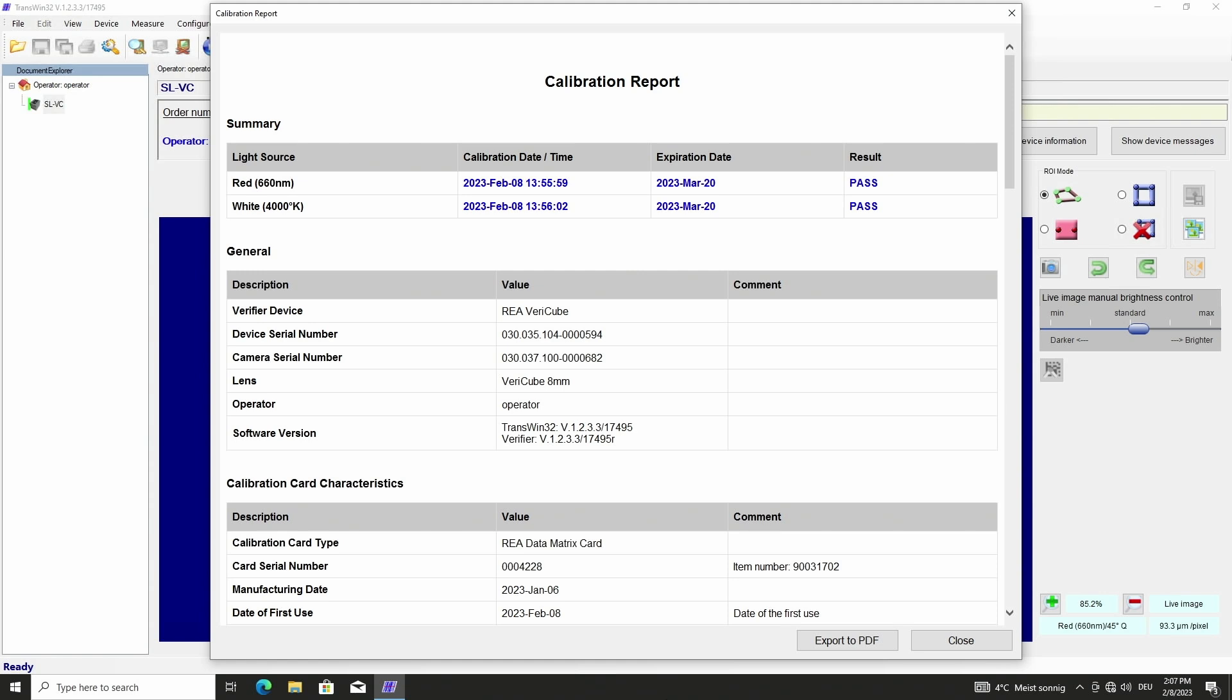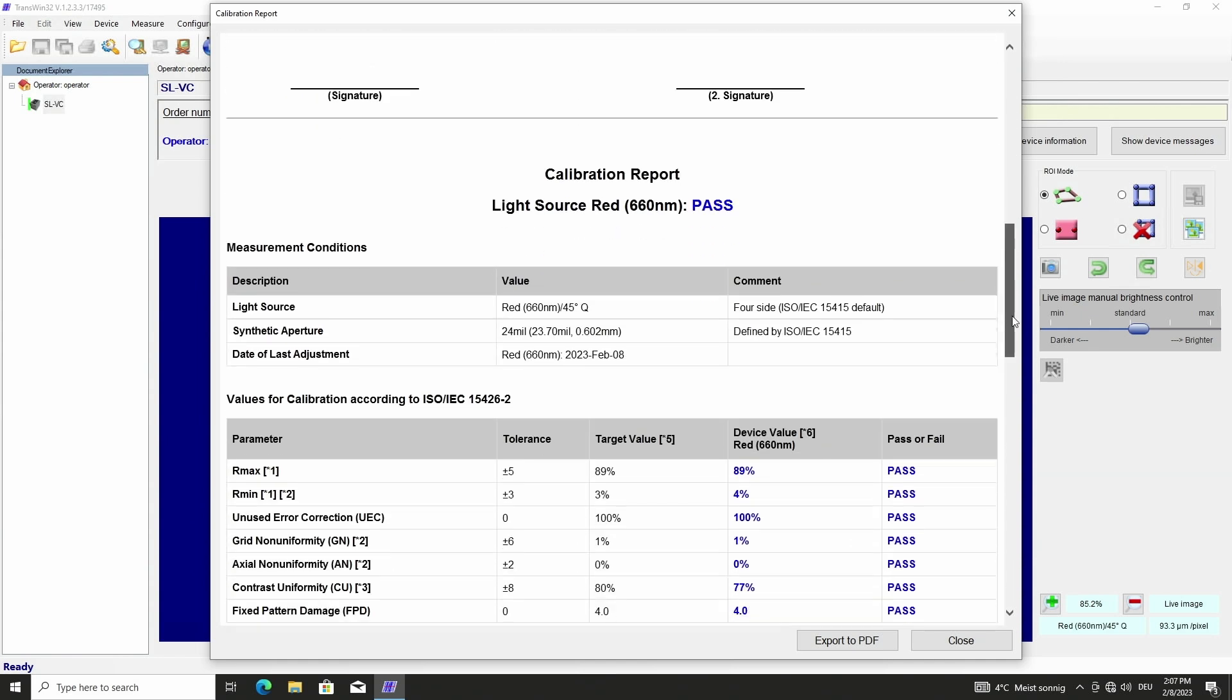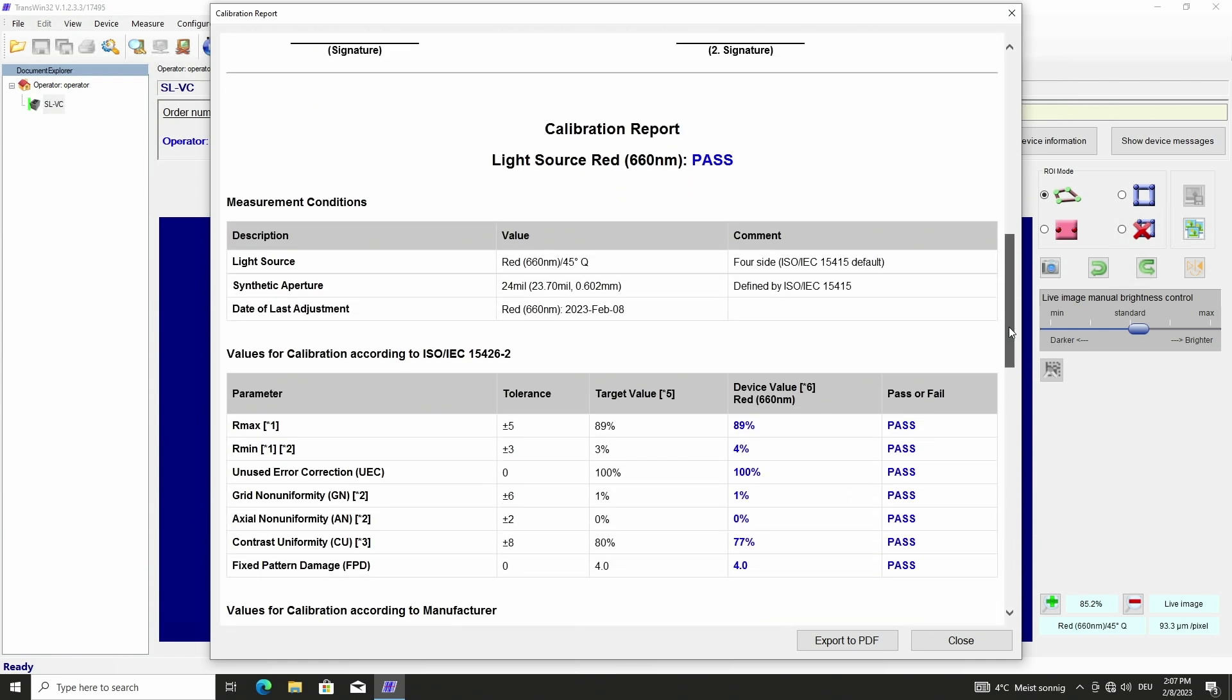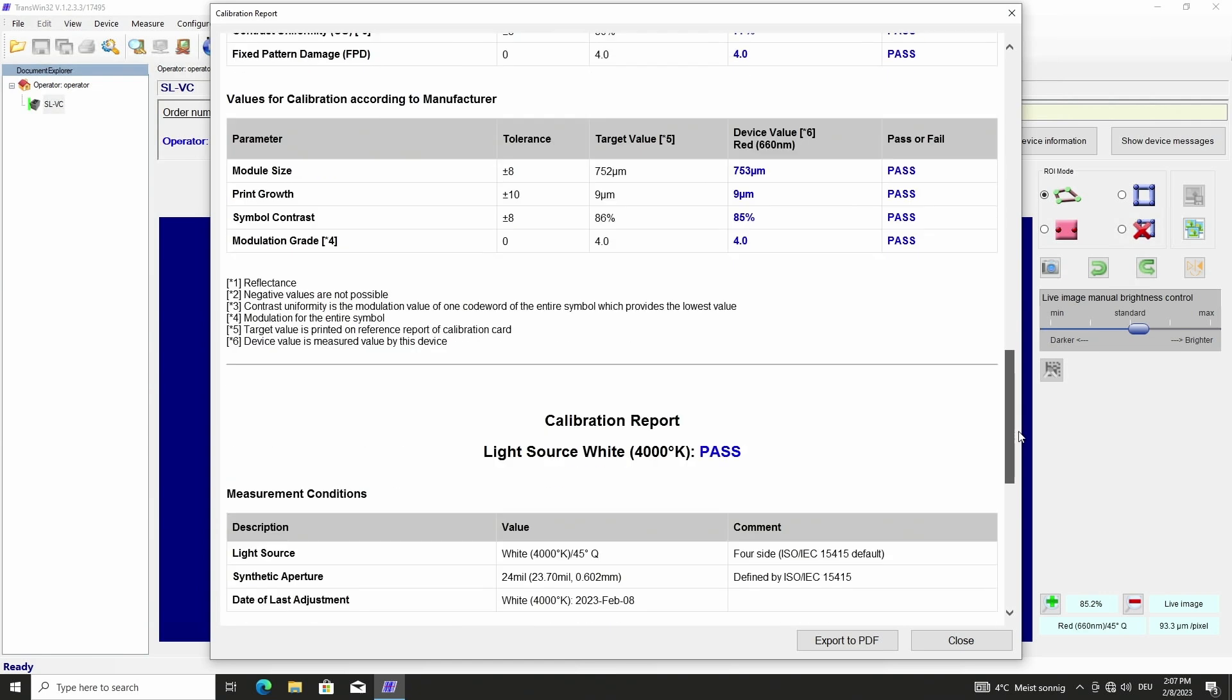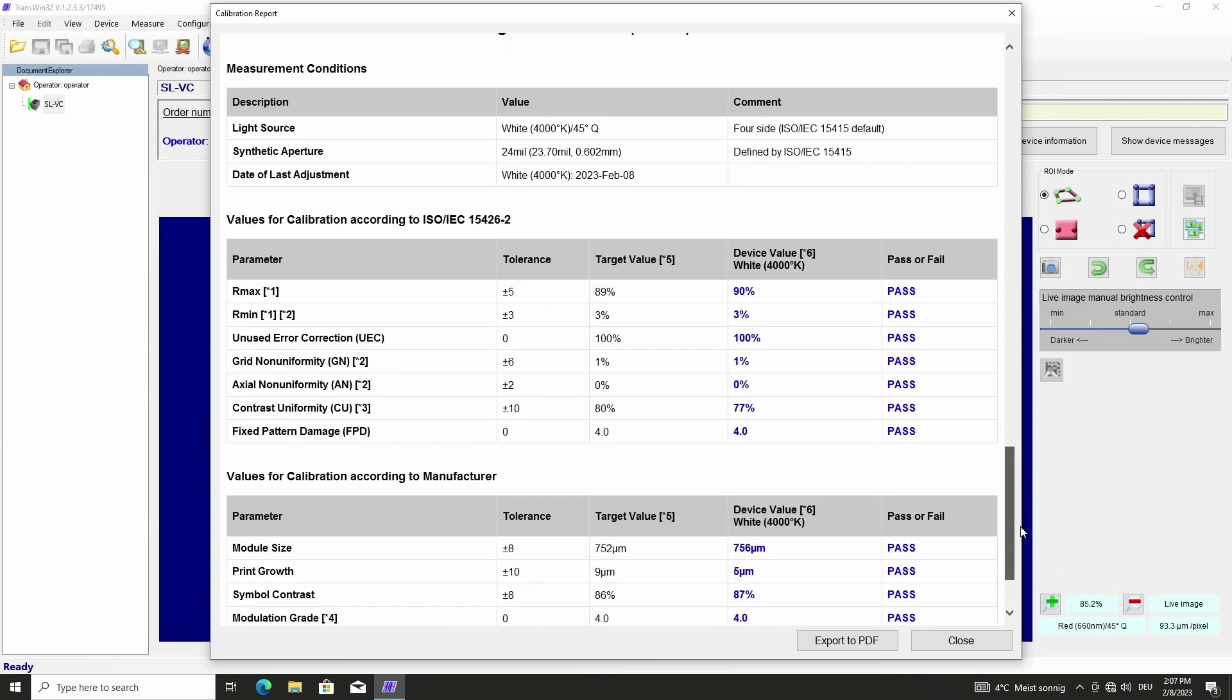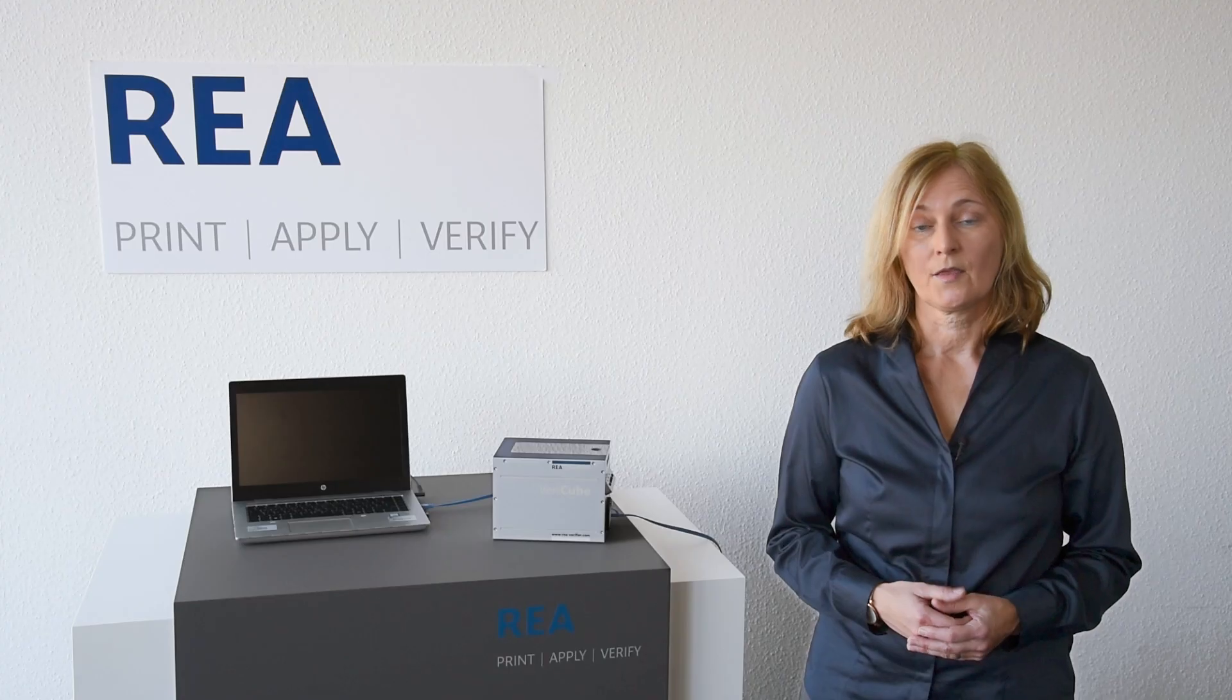A calibration report is automatically generated that shows clearly the result pass or fail in the header and in the following we see the individual calibrated parameters for red and for white light source. The calibration report can be exported to PDF. Only the latest calibration report is stored in the software itself.